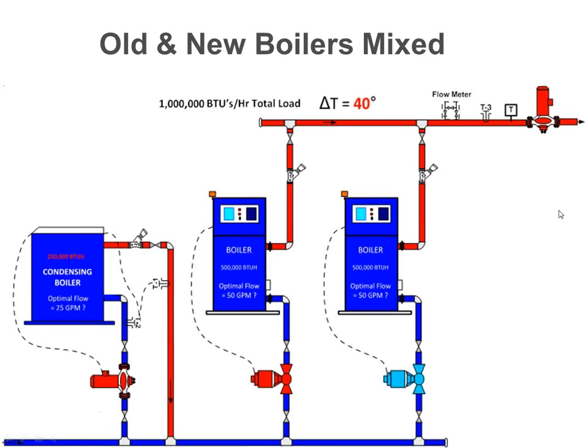When you're dealing with new boilers and new boiler systems, you do not have to go strictly cast iron, 80-some% efficient, or strictly all condensing boilers. It's very easy to put a condensing boiler up front of the system and keep your old cast iron boilers for the really cold days. So what happens most of the time is the condensing boiler handles the heat loss of the building.